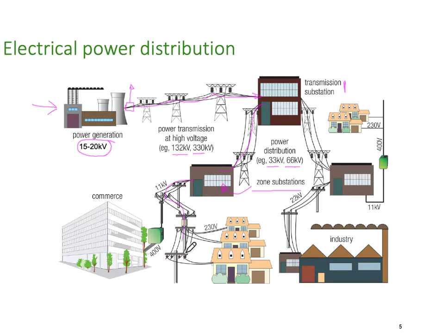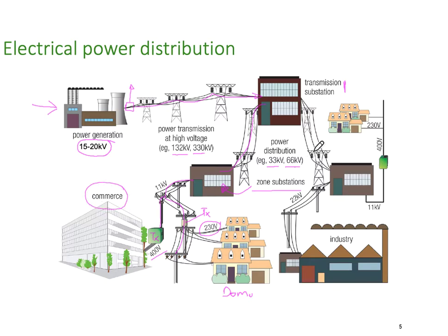The power comes along the tops of poles. There's another transformer here — I use the abbreviation TX for transformers — and it breaks the voltage down to about 230V single phase to supply domestic houses. Also coming down through another, larger transformer, supplying 400 volts into a commercial building. Coming down the far right-hand arm, we come down to another zone substation, and here we're distributing out at 22 kV.